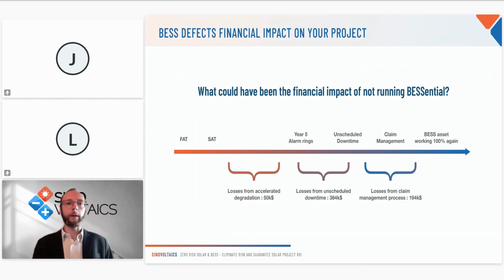In our case, we consider that after the SAT, during 5 years, the battery pack will degrade faster than the others because of the temperature issue, but during those 5 years it works normally - not detected by any BMS or alarms. Then, starting in year 5, there's an alarm one day. No one knows where it's coming from - a safety alarm, a thermal alarm. Because the client is afraid of potential thermal runaway, he decides to stop the project until he understands what's going on.